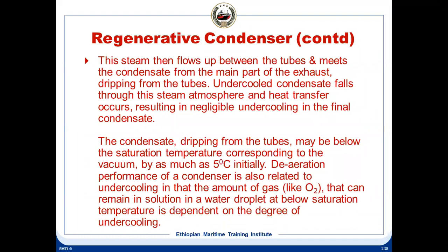And deaeration performance of the condenser is also related to undercooling, in that the amount of gas, for example oxygen, that can remain in solution in a water droplet at below saturation temperature is dependent on the degree of undercooling. That means the more the undercooling, the lesser the temperature below 100 degrees centigrade, the greater the chances of gases like oxygen being dissolved in the condensate. And being dissolved means these gases will obviously go to the boiler, unless we have regenerative condensers or deaerators. Deaerators also act as a feed water preheater.